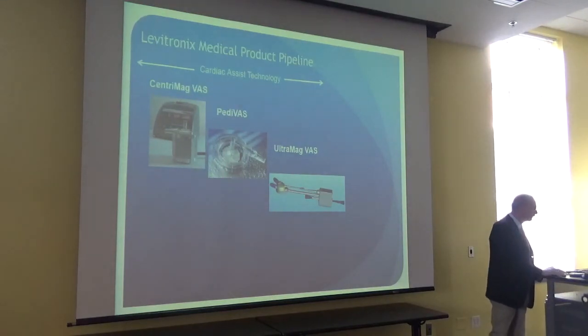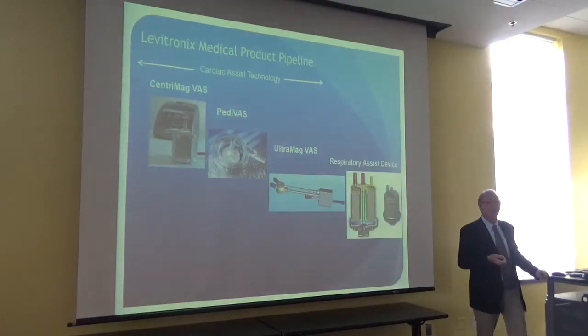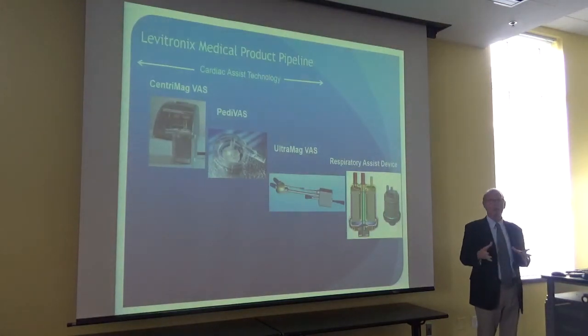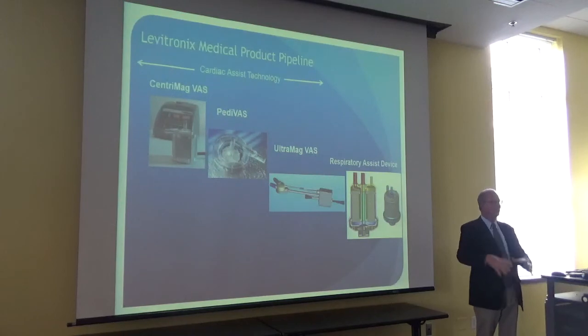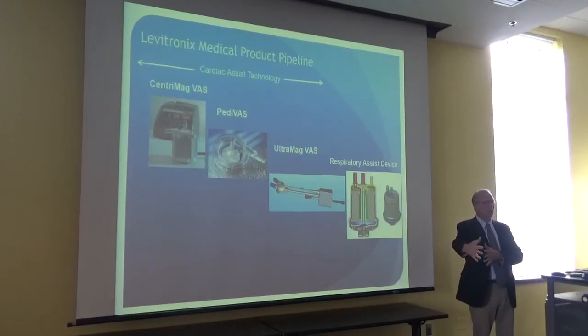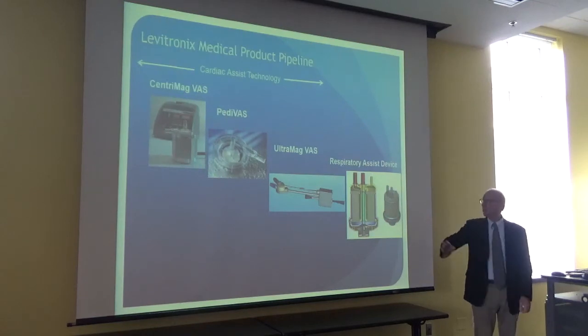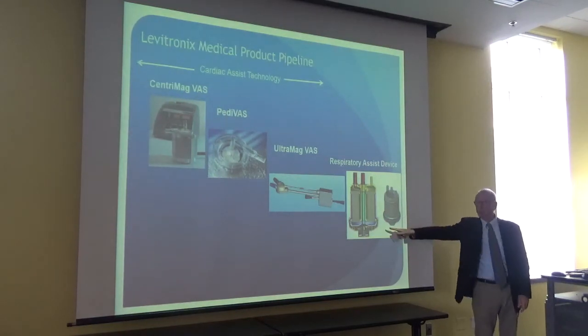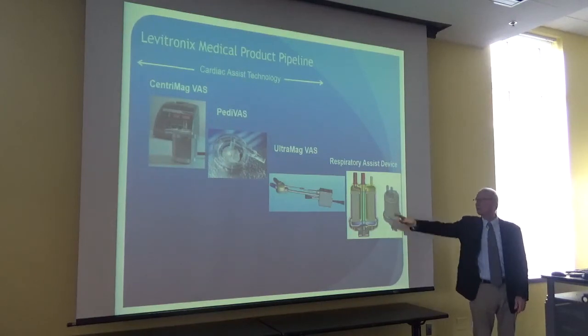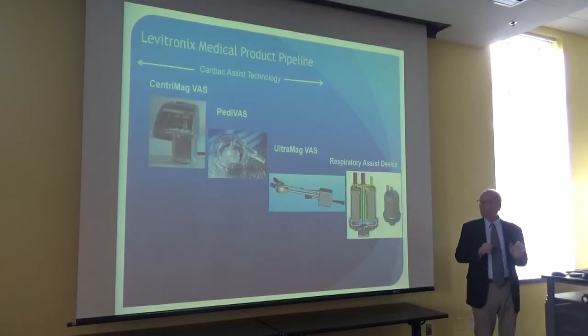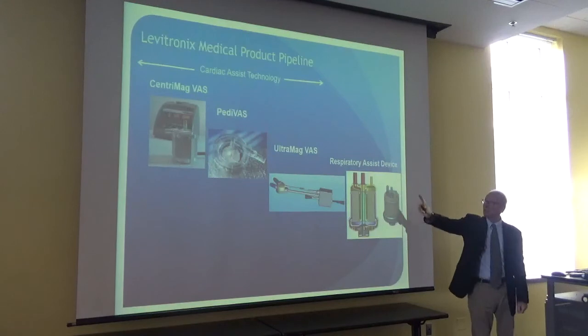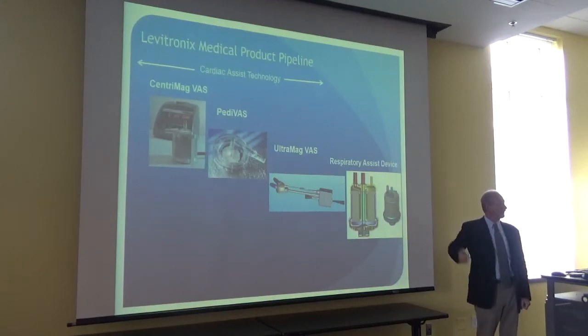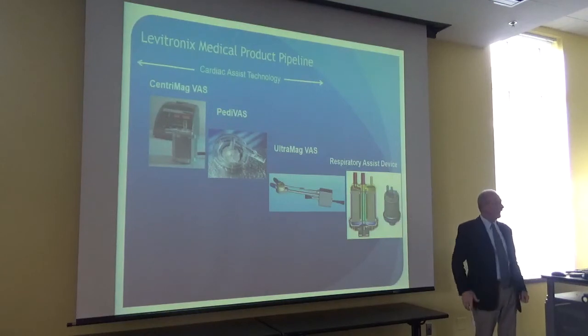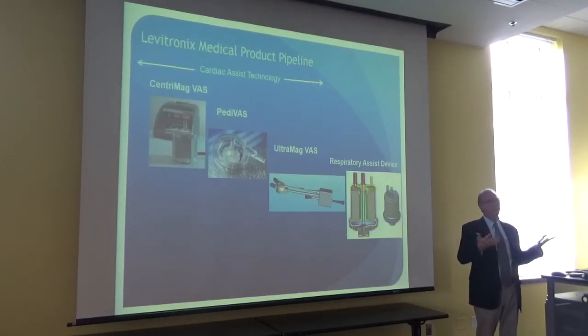Similarly, we developed a respiratory assist device. Anyone who knows the ECMO space knows you have a pump, an oxygenator, a heat exchanger, with tubing and connectors between them. What we did with this device is integrate a pump, then use state-of-the-art hollow fibers made of polymethylpentene, and even incorporate a heat exchanger into a single module. That module could be placed into the motor of the CentriMag or the Ultramag, and it could function as either a wearable or bedside ECMO unit.